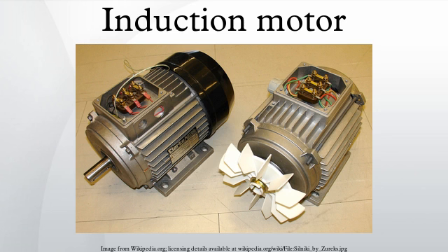Starting. There are 5 basic types of small induction motors: single-phase capacitor start, capacitor run, split-phase and shaded pole types, and small polyphase induction motors. A single-phase induction motor requires separate starting circuitry to provide a rotating field to the motor. The normal running windings within such a single-phase motor can cause the rotor to turn in either direction, so the starting circuit determines the operating direction.